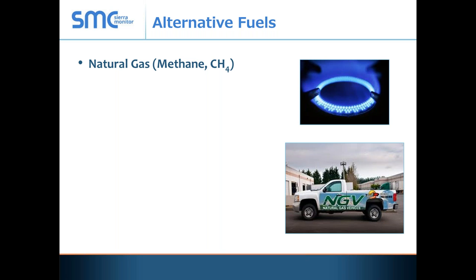Natural gas is what you see in your kitchen used for cooking. It is also used as a fuel for vehicles. When I say 100% LEL, I mean that's the level it takes of gas to be explosive — what we call the lower explosive level — that's 5% by volume. It is a fuel that is lighter than air, so it's not going to stay on the ground; it's going to seek the highest point in a facility. It is odorless. The smell you notice in your house is added to that gas. Real natural gas does not smell.